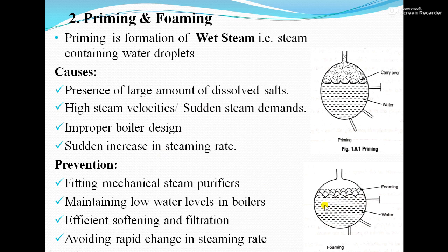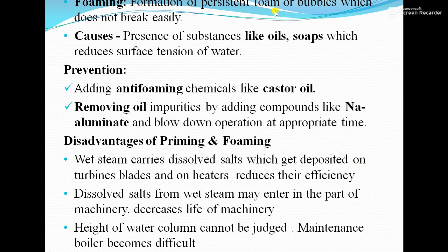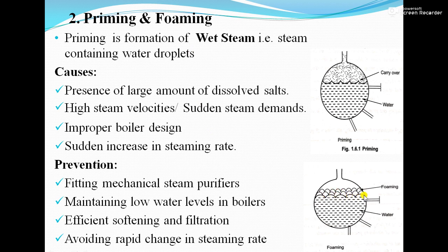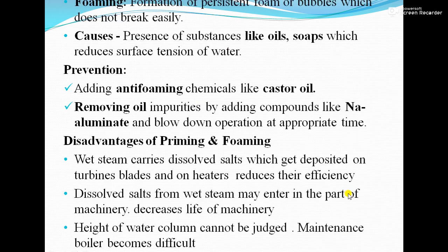Foaming is the formation of persistent foam or bubbles which do not break easily. The causes of foaming are the presence of substances like oil and soaps, which reduce the surface tension of water. Prevention: add anti-foaming chemicals like castor oil, and remove oil impurities by adding compounds like sodium aluminate, along with blow-down operation at the appropriate time.